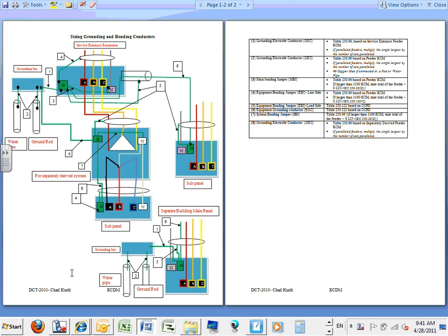Grounding and bonding, guys, Article 250. Let me just quickly repeat what I said a second ago. We have a service. If you guys can look right in here, you have your service. This is my service entrance coming to the building. From the service, I took a feeder and fed my mechanical panel or lighting panel, any other sub panel.